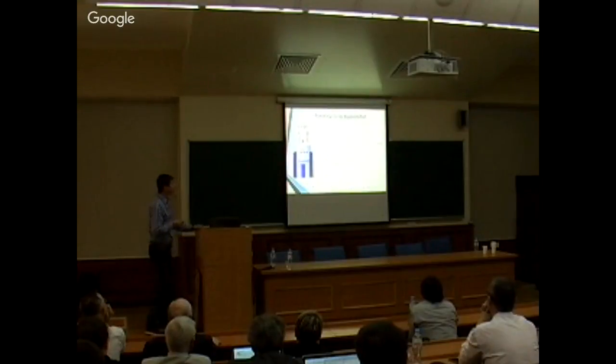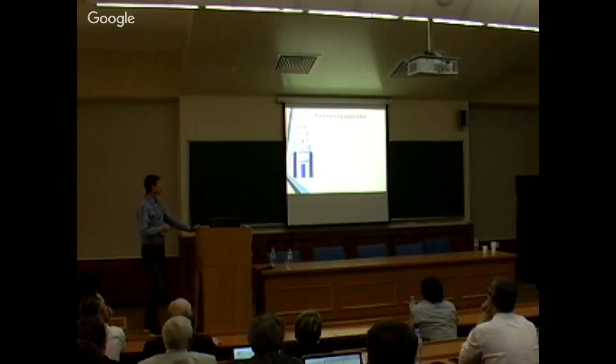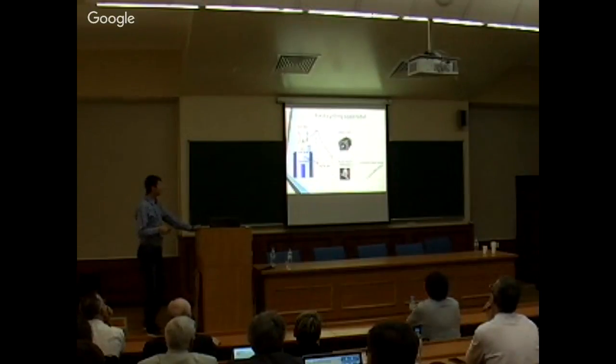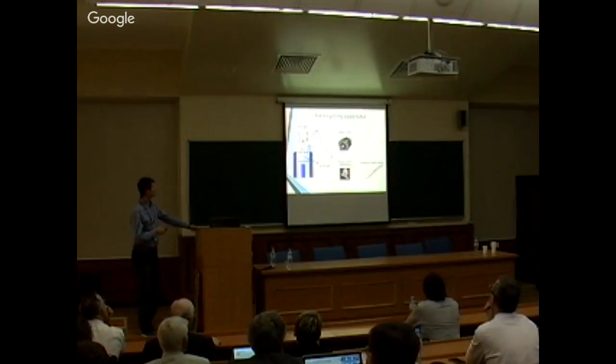You need an apparatus where you can easily change the magnetic field. So we decided to build in our institute an apparatus which is quite unique. First of all, we use the stray field from the cryomagnet, which drops from 9 Tesla to about 2 millitesla with distance. We move, or shuttle, the NMR sample by rack and pinion transmission using a stepper motor, which is controlled from an NMR console.